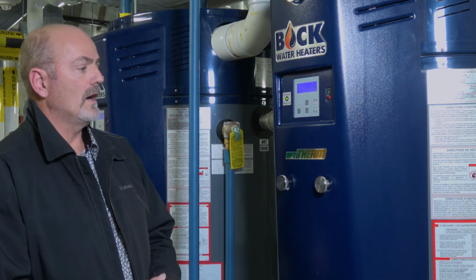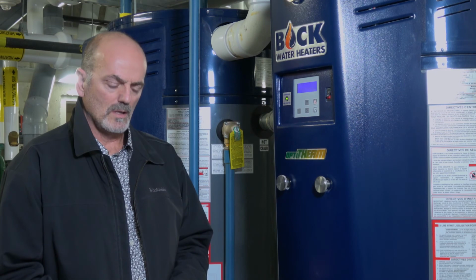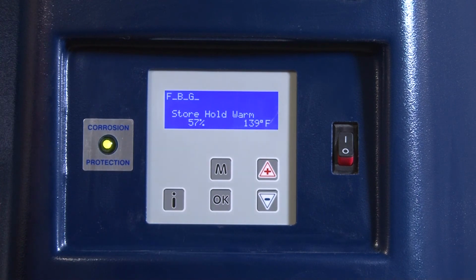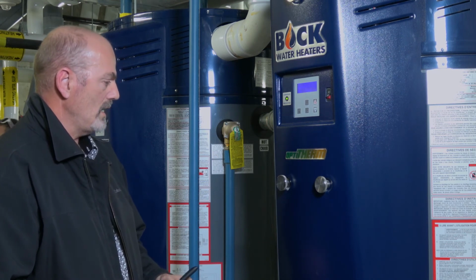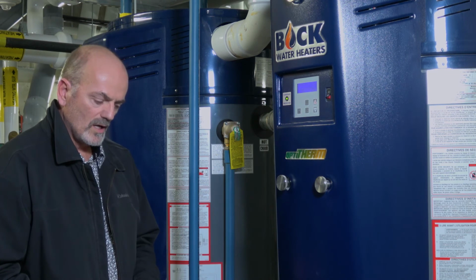It does have a condensate drain connection similar to the boilers, and that condensate connection is hooked up to a condensate neutralizer, which makes sure that the water coming out of the condensate is neutralized, not acidic, okay? If that condensate neutralizer becomes plugged, then it needs to be addressed because it can back up into the exhaust connection and cause the heater to shut down. That will show up here as a fault as well, okay? The media in the condensate neutralizer does wear out over time and you do need to replace it, and the only way you can determine that is by a maintenance contractor or on-staff maintenance using pH strips. They can check the condensate that's going down the floor drain from the heater, and that will tell you if it's pH neutral or not. If it's not, then you need to replace the condensate neutralizer media, which can be done quite simply by in-house staff or by a service dealer.